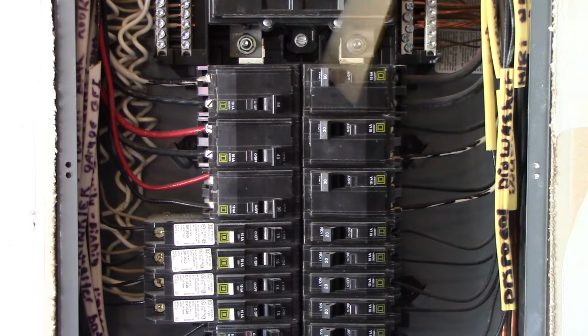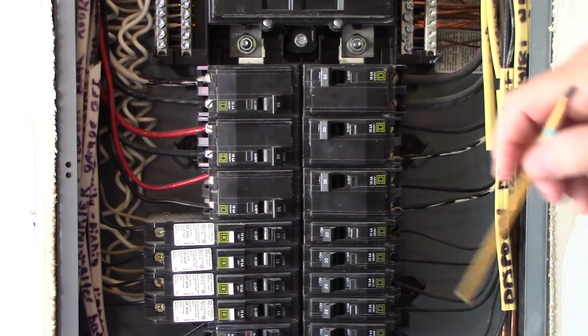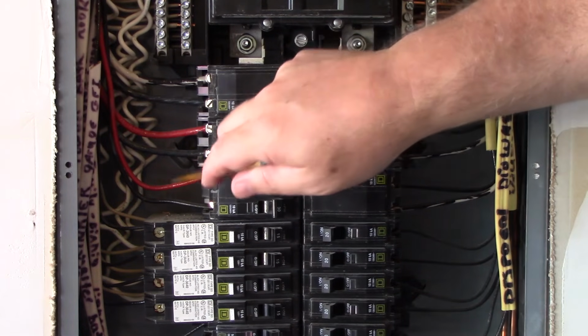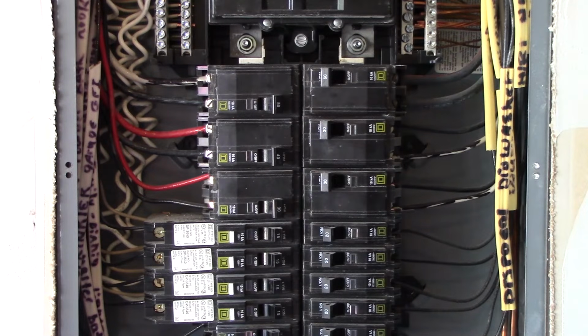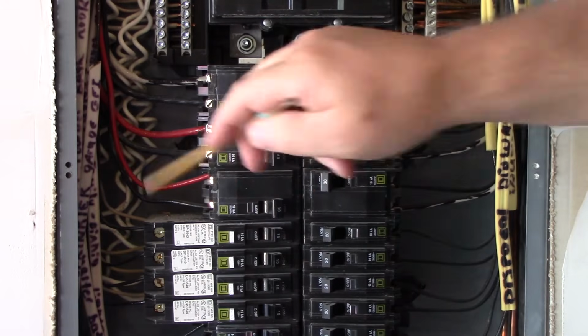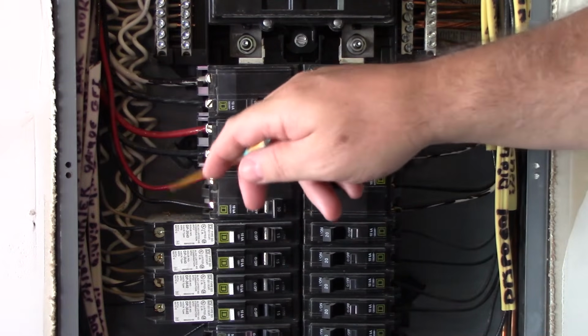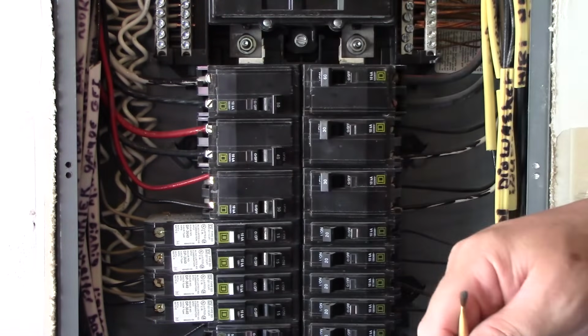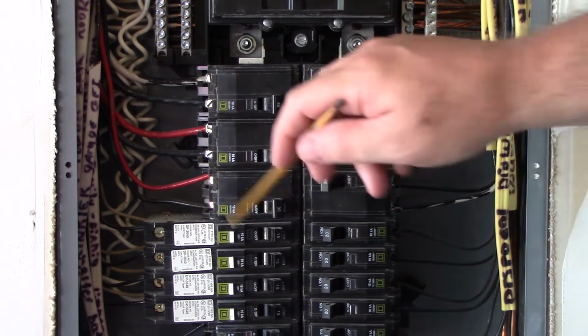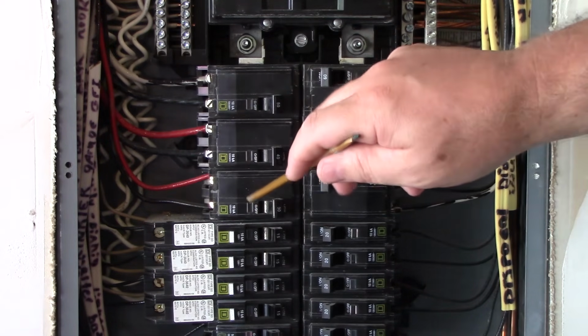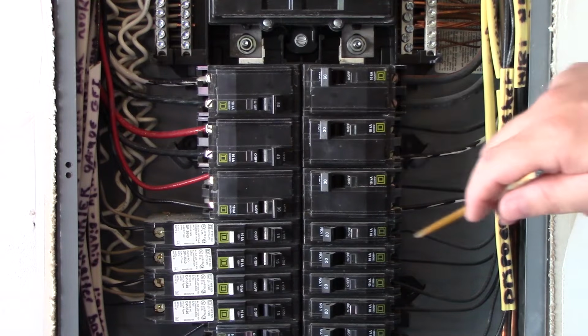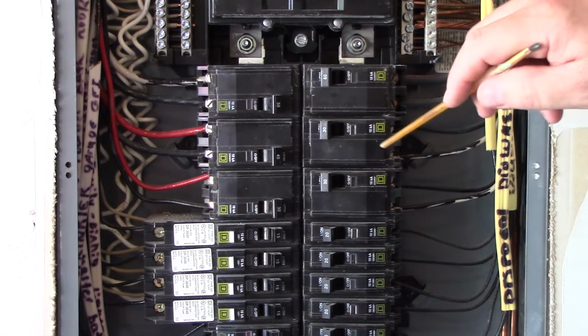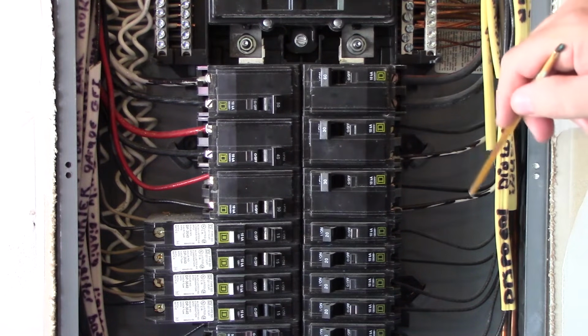So over here, we know they're all copper, so in that application, even our SE cable in this case is copper. All right, so here's a 30, and we know this here is a 10 gauge. I can actually see some of the orange sheathing, but if I didn't see that, I can tell by the size. I'm familiar with that size, as opposed to a 12, versus going up over the 10 to an 8. I can tell that this is a 10 and it's on a 30, so that's okay. Here's another 30 and this is a 10. And here's another 30 and this is a 10.